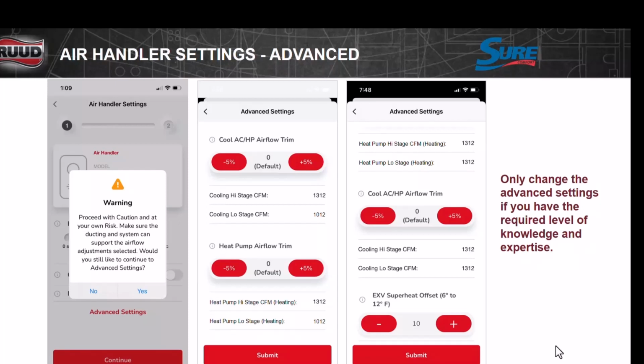When I say trim, we can raise or lower the airflow in 5% increments up to 25 percent minus. Because you may have a unit that's putting out 1,312 CFM like that one's doing, and today we're not going to have much dehumidification on a 3-ton unit, right? At 1,312 CFM. So we need to drop that down a little bit to get it below probably about 1180 or somewhere around there, so we can get our 350 CFM per ton, which is basically where we want to stay down here. Well, I mean, it works. You get a lot of sensible cooling out of it, but you don't get any latent. You can tell the difference.